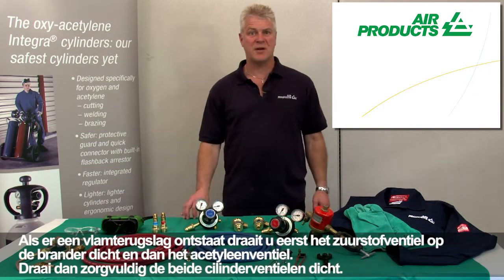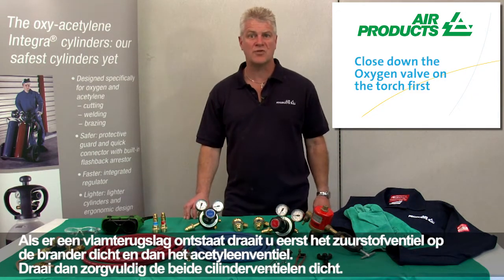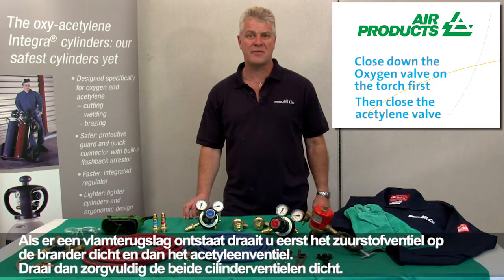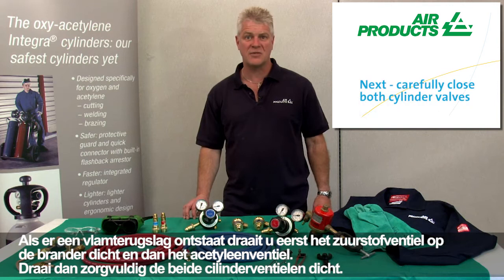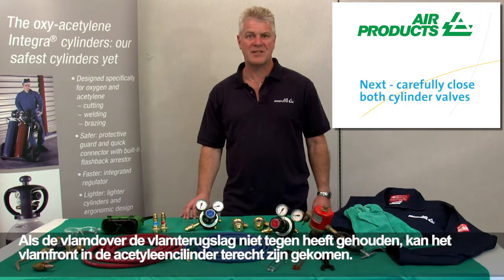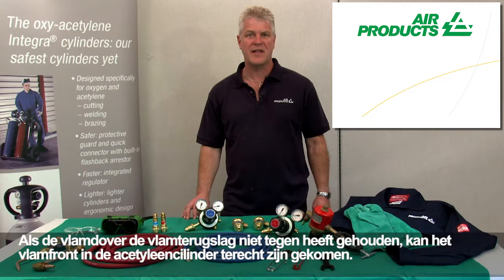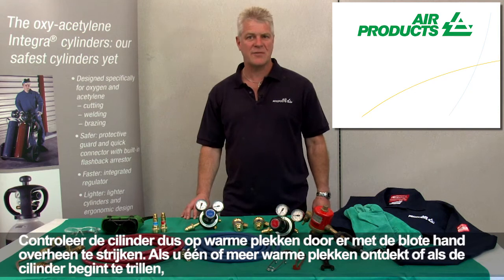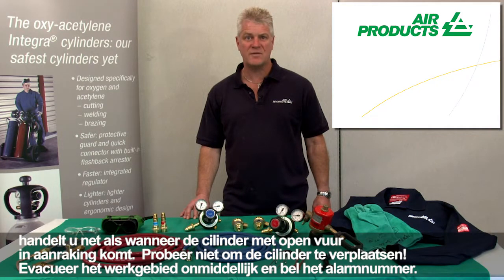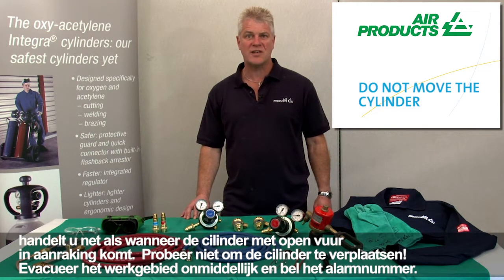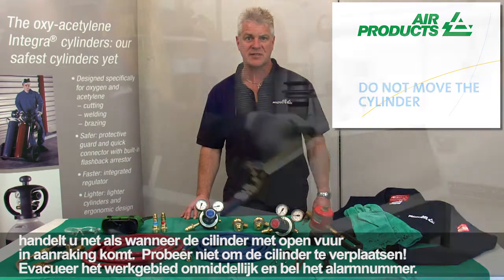If you get a flashback situation, close down the oxygen valve on the torch first, then close the acetylene valve. Next, carefully close both cylinder valves. If the flashback arrestor didn't stop the flashback, then the flame front may have entered the acetylene cylinder. Now check the cylinder for hot spots by running a bare hand over its surface. If a hot spot's detected or the cylinder begins to vibrate, treat it as if it's been involved in an external fire. Do not attempt to move the cylinder. Evacuate the area immediately and call the emergency services.